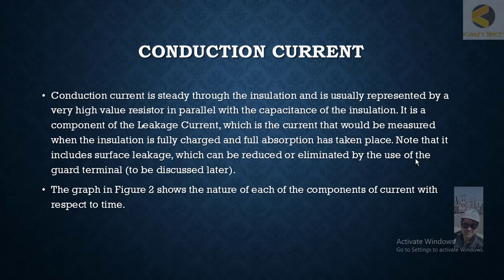Conduction current is steady through the insulation and is usually represented by a very high value resistor in parallel with the capacitance of the insulation. It is a component of leakage current, which is the current that would be measured when the insulation is fully charged and full absorption has taken place.